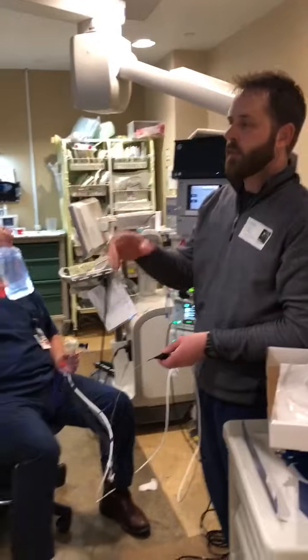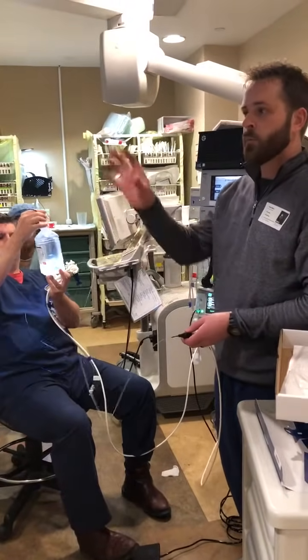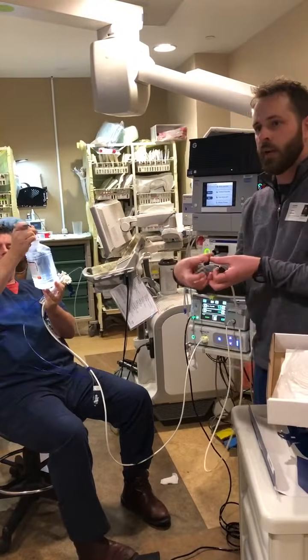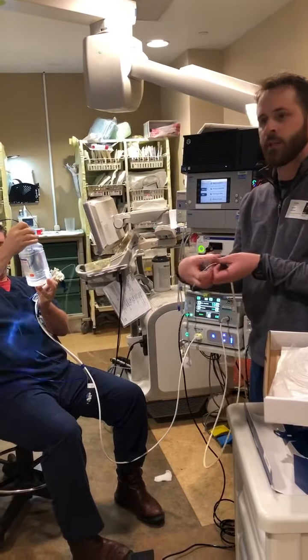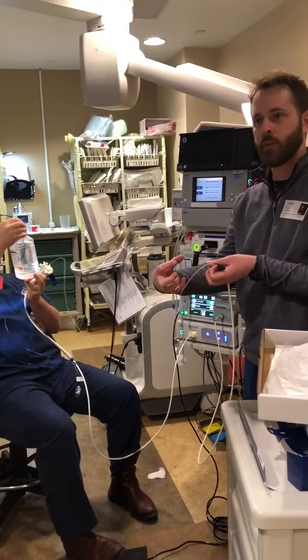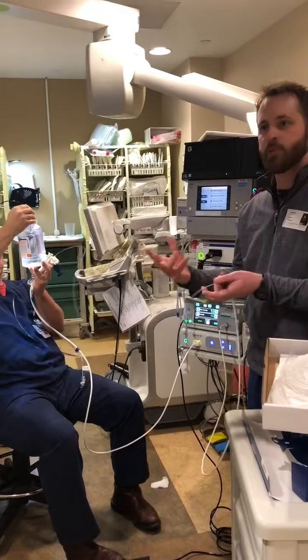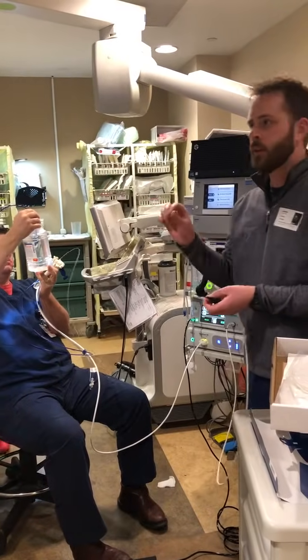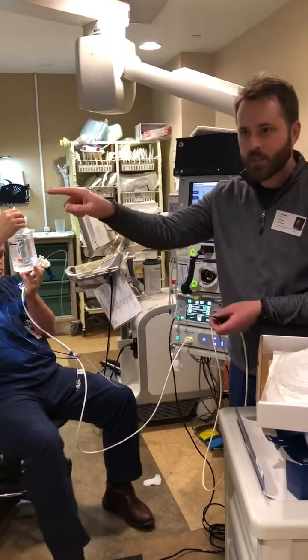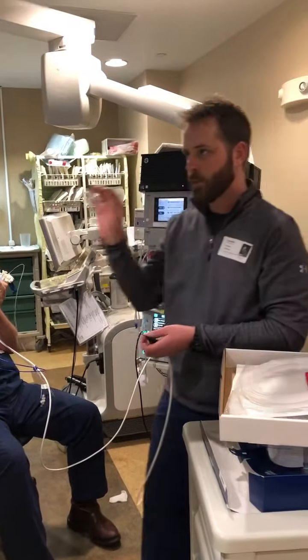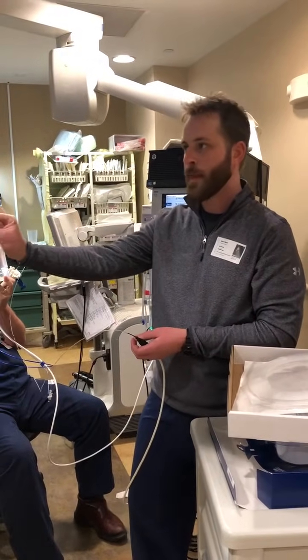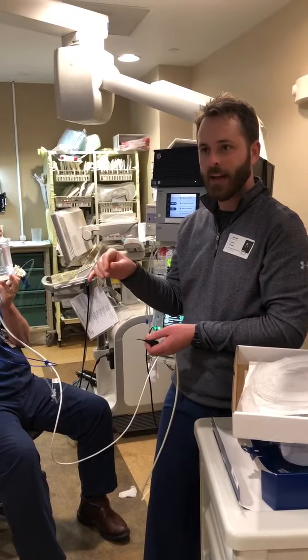So this is a tip that Dr. Rastogi and Dr. Ollier know, but with this device, basically we're creating a bubble between the probe and the stone that we're trying to break up. When that bubble explodes, that's what cracks the stone. So this probe, you don't want it touching the stone. What most docs will do is they'll push the probe out, they'll touch the stone, and they'll back up about 1 millimeter and then activate it.